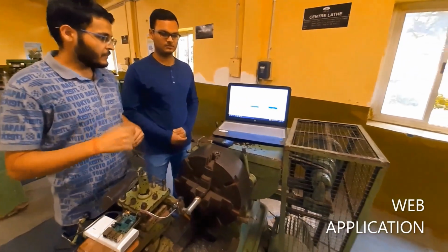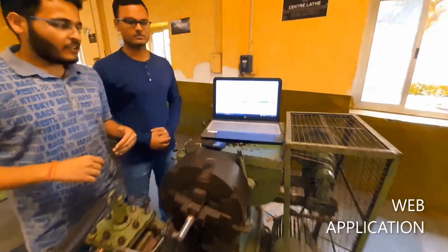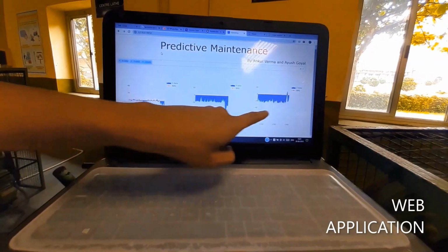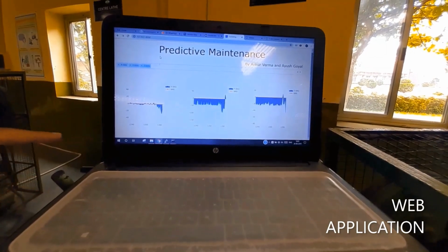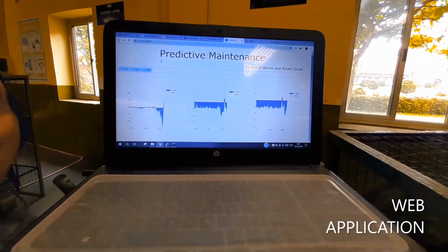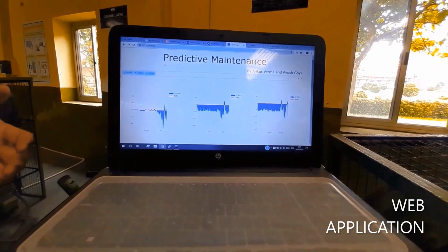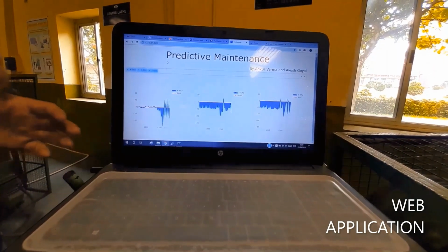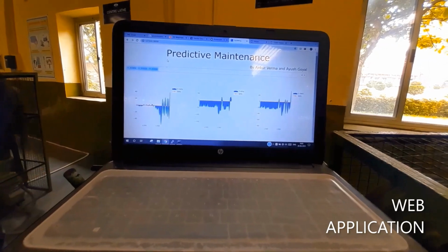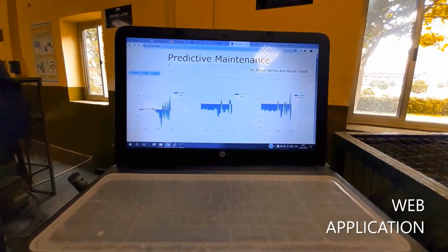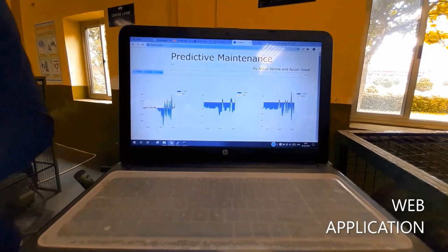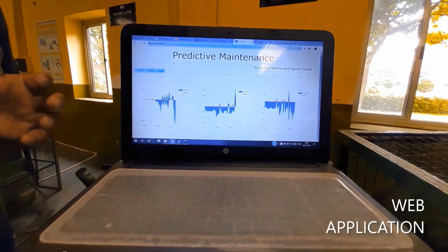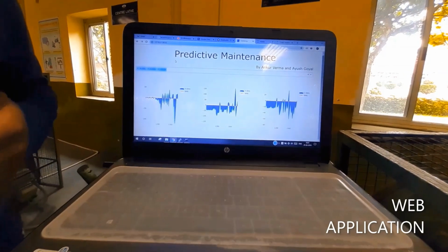As we turn on the machine, there would be an initial jerk. Now we can clearly see there is a spike on each of the x-axis, y-axis and z-axis which shows this jerk. This jerk is basically because of the sudden movement of the machine and its components once we have started the motor. Also, in the time domain spectrum of this signal, we will be able to further see several peaks and valleys, which will represent several imperfections in the spindle as well as some of the problems in various parts of the machine like gear, pulleys, motor, etc.